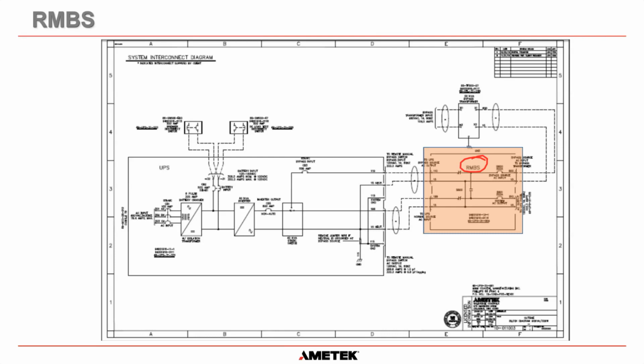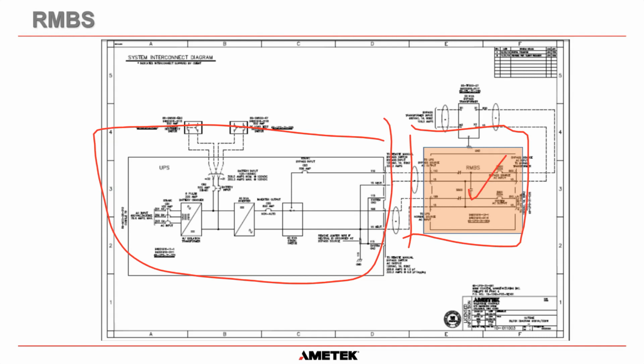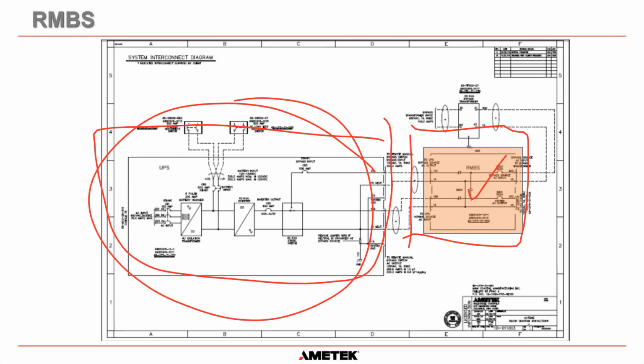Okay, so this drawing here, it's the same UPS that we had before. Power flows out through this terminal here, out through our remote manual bypass switch, and you can see that that contact there is closed, so it will go out through here and out to our load circuits. Okay, and then on this system, our bypass goes through a transformer. It comes down here, goes through the RMBS, and this is closed, and it goes and supplies the bypass to the static switch. Okay, and this contact here is open, and we'll explain that in just a moment. But you can see now that the bypass switch is completely separate from the UPS. Here's our UPS enclosure here. This could be in a different room if necessary. In most cases, it's right next to the UPS, but it is not physically connected to the UPS usually. It is remote, and therefore, if we follow the procedures, we can actually make this whole UPS volt-free and work in it safely.